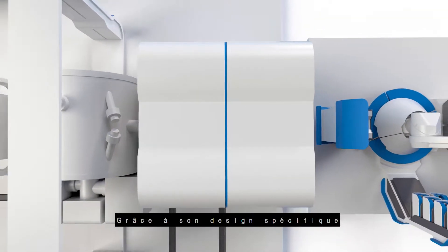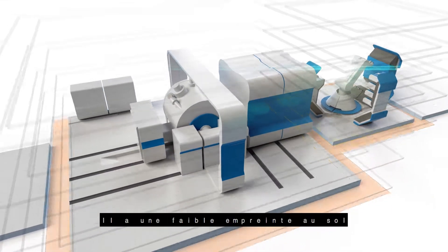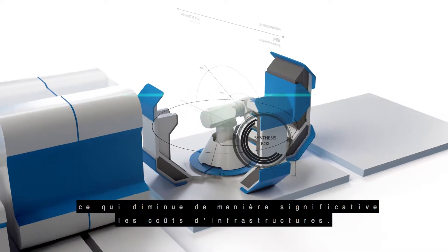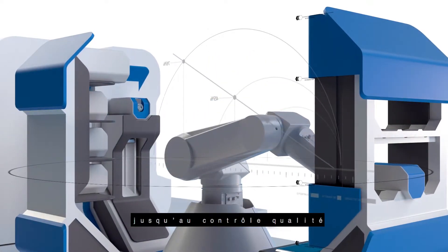Because of its specific design, iMiLab is the lightest self-shielded system in the world. It has a small footprint and can be installed within 40-centimeter walls, which greatly reduces infrastructure costs. From synthesis to syringe filling until quality control, no human interaction is required.